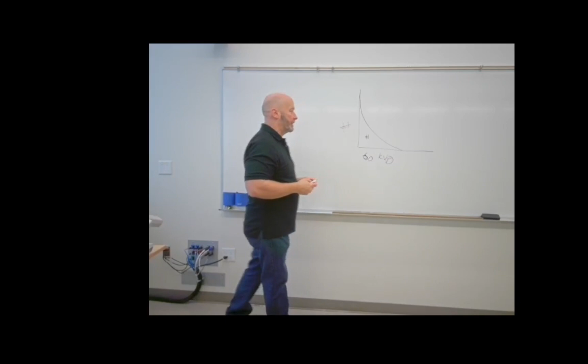You remember? Specific energy level. Somebody said 69, right? So 69 kVp. So if you set 68 kVp on your control panel, and your machine is actually working accurately, then you don't have a characteristic spectrum. If you recall, let's say this X-ray beam here is maybe, we'll say 60 kVp. If you recall, our characteristic spectrum is going to be recognized as just a little spike, right at 69 kVp. So at 60 kVp, we don't have a characteristic spectrum.